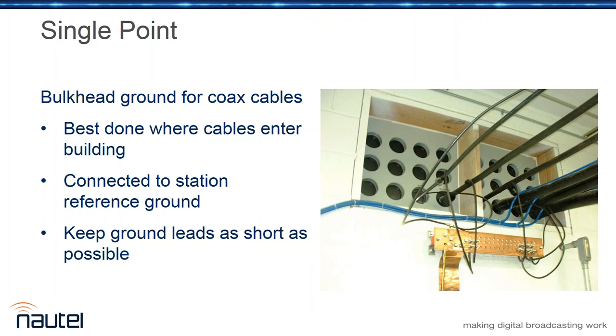Where should ferrites be installed - on AC cables to tower lights or to cables for STL gigahertz radios? The short answer is, for AC cables to tower lights, they'll go through a lightning choke of some kind, whether it's a bifilar lightning choke, an Austin transformer, or whatever. Typically, I'd put those ferrites toward the transmitter building, probably right in the transmitter building itself. For cables for STL gigahertz radio, same basic deal - if the coax is grounded where it enters the building, then I'd want the ferrite between the radio and the grounding of the coax shield.